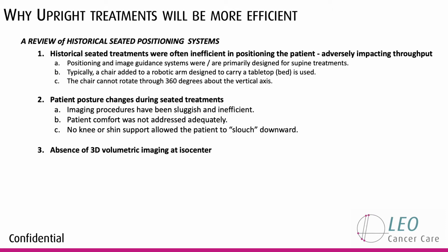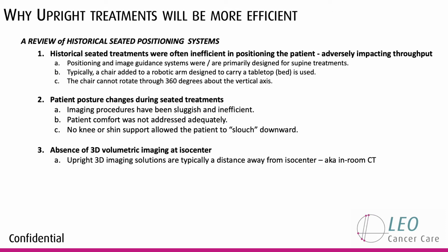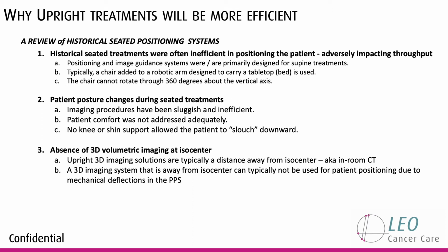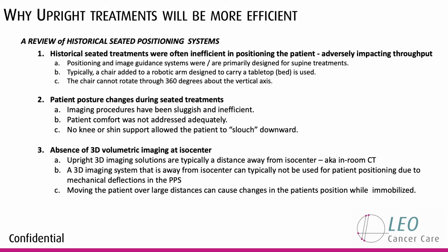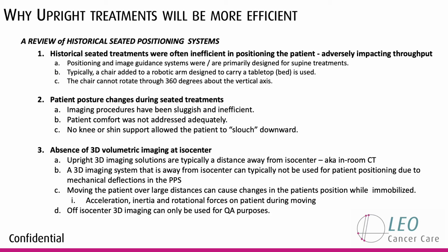Another big thing of historical systems is the absence of 3D volumetric imaging at isocenter. So upright 3D imaging solutions are typically at a distance away from the isocenter, so-called in-room CT, and that's also the case for the upright CT scanner in Chicago. A 3D imaging system that is away from isocenter can typically not be used for patient positioning due to the mechanical deflections of the PPS. So if you have to transfer the patient to the other side of the room, these mechanical arms always have significant deflection as the center of gravity moves further away from the mounting point. And also moving a patient over large distance can cause changes in the patient's position while immobilized. And that's of course due to acceleration forces, inertia, and rotational forces on the patient during the movement.